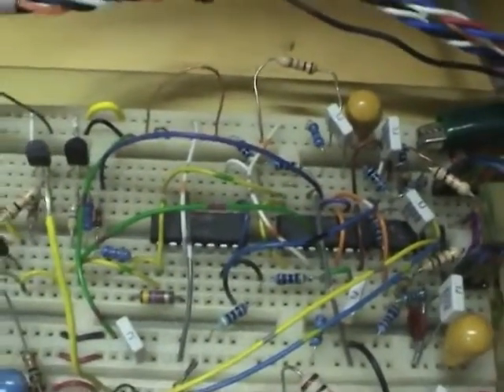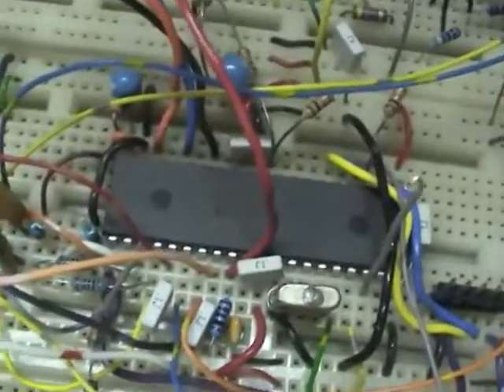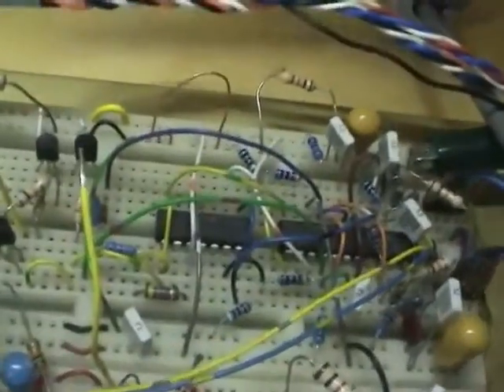What else have we got? On the motor down here, let's see if we can see this, there's an encoder to measure the speed. That just wires up to a detector circuit comparator over here. There's also current transducers, one on each, or two on A and C phases, and those run over to an amplifier, and the amplifier sends the signal to the ADC. There's a hardware comparator circuit that will shut the output down if overcurrent is detected, independent of the micro. And I'm sure that has saved the power stage numerous times.